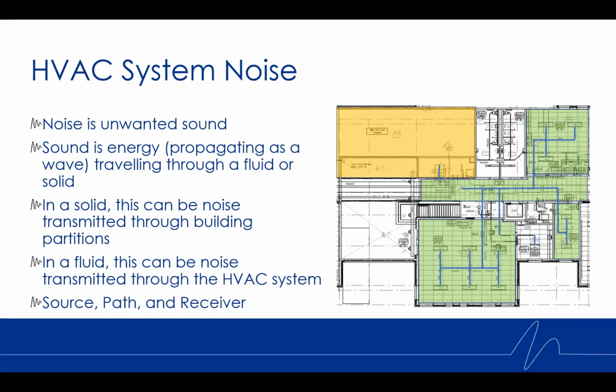So when that sound energy is transmitted through a solid, and for the purpose of looking at a building, that's going to be your building partitions. That's going to be when the vibration travels through the floors and the walls. And then when it travels through a fluid, this is going to be the air. So when the air is traveling through the ductwork, when the air is being exhausted, or the outdoor intake, the sound is traveling through those paths as well.